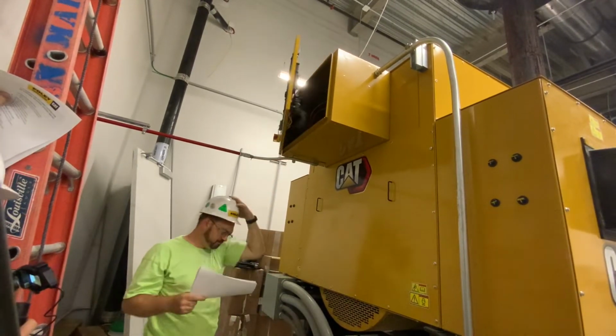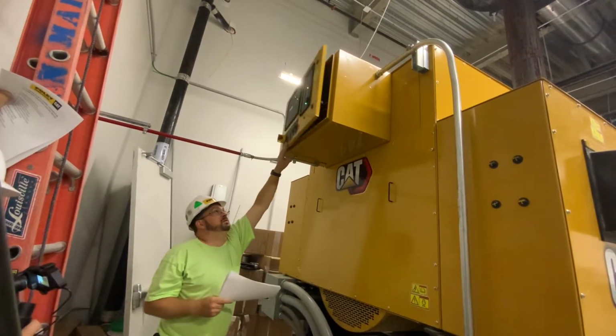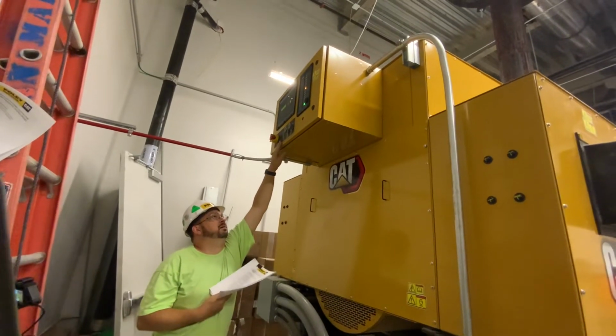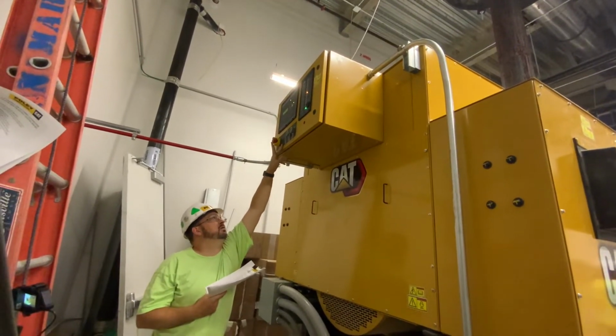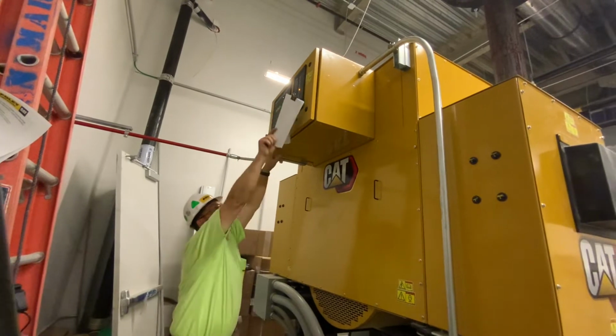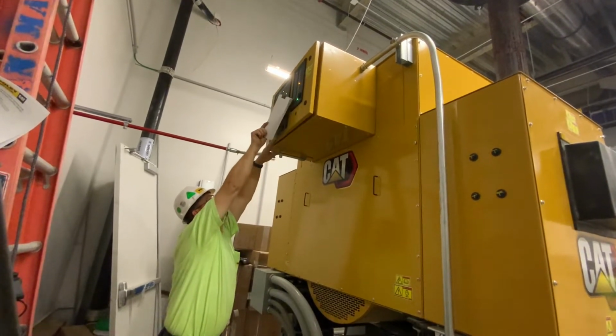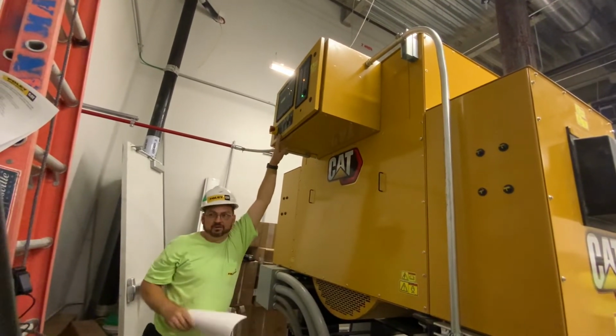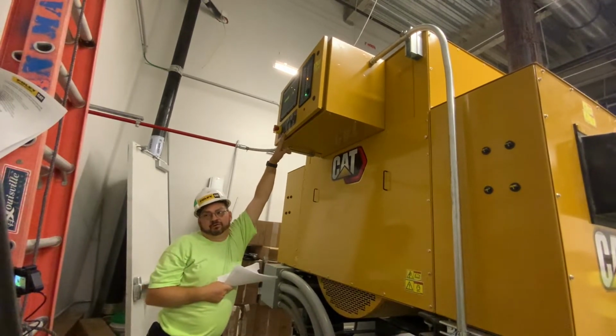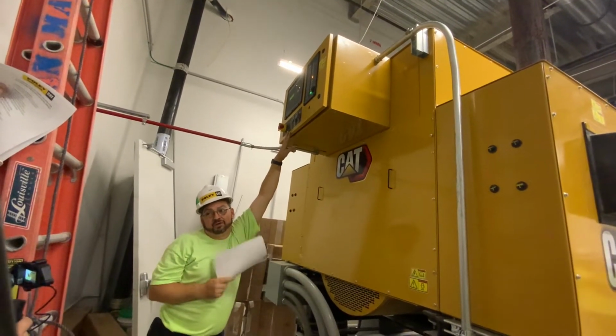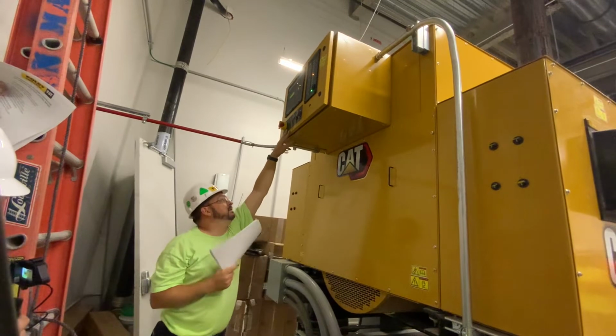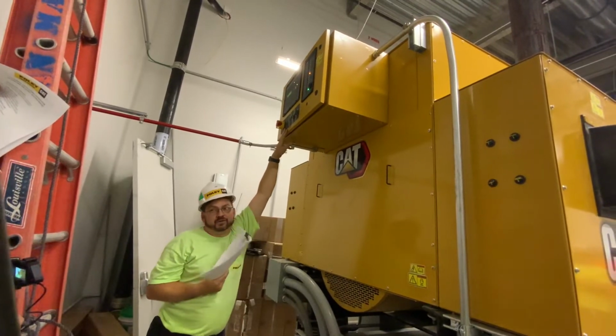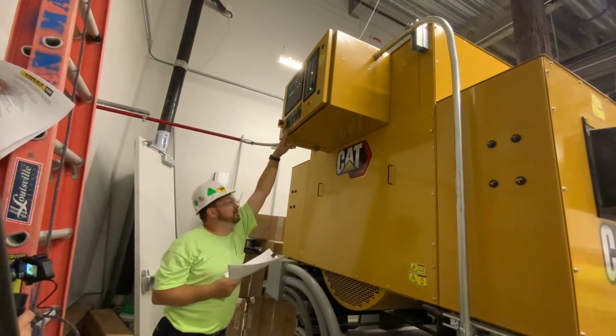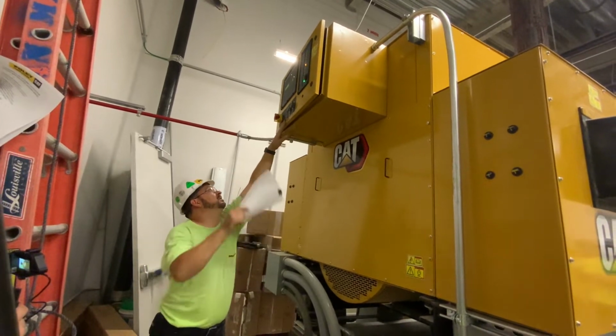If for some reason you had a shutdown or a warning that wasn't listed on your annunciator, you could go into your event log by pushing that button, and it would show you what the cause is. About 90% of them are on the annunciator; however, some things like senders, when they go bad, trigger a diagnostic fault that doesn't show up on the panel.